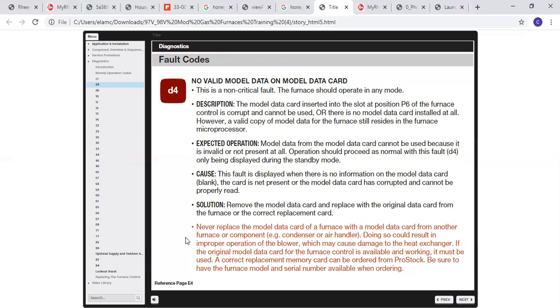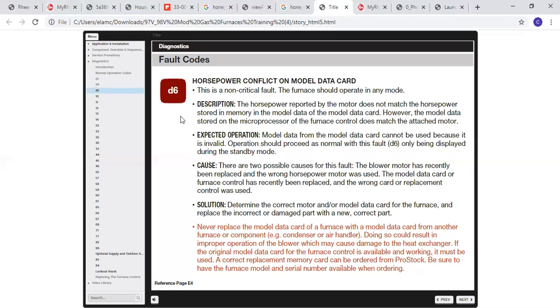Now, in red down here at the bottom, this is huge. Never replace the model data card of a furnace with a model data card from another furnace or component, e.g. air handler, condenser, heat pump. Doing so could result in improper operation of the blower, which may cause damage to the heat exchanger. Usually, if you use the incorrect model data card, it's going to give you an error code and it won't even work. But people try.